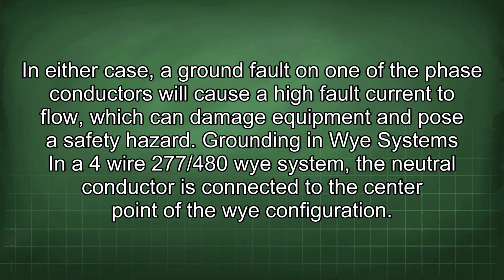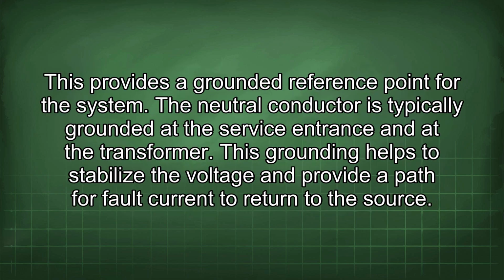Grounding in Y systems. In a 4-wire 277/480Y system, the neutral conductor is connected to the center point of the Y configuration. This provides a grounded reference point for the system. The neutral conductor is typically grounded at the service entrance and at the transformer. This grounding helps to stabilize the voltage and provide a path for fault current to return to the source.